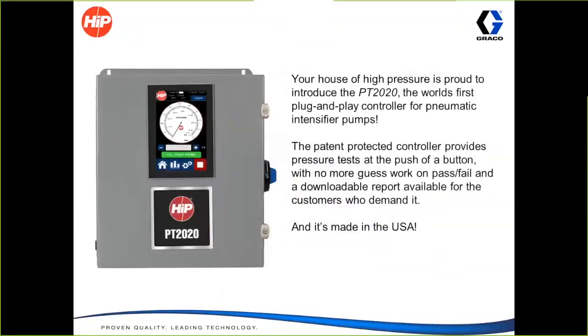The PT2020 is recently getting introduced, and it's our first plug-and-play control box for intensifier pumps that allows you to automate your process. The box has a patent pending currently. This basically allows you to automate your test whenever you're doing any hydrostatic testing. So it takes any guesswork out when it comes to a pass-fail criteria, and not only that, but gives you a downloadable report that you can hand over to your customers.